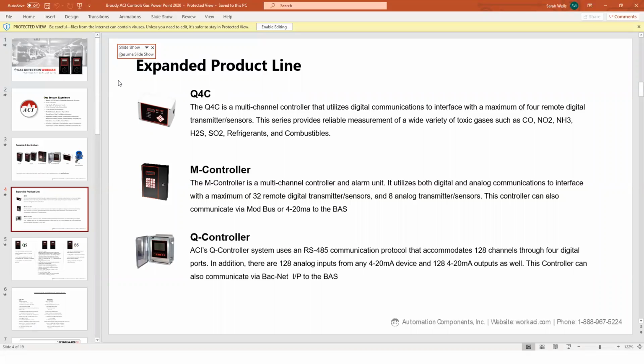The 3 different controllers, we just kind of covered those. Q4C, which is a 4-channel, multi-channel controller, digital communication, just for really, really small jobs. For the cost, I tend to stay away from it. I tend to try to push customers into the M controller. It's more flexible with the inputs, outputs, and the 32 remote digital covers a lot more projects. You can also have analog output cards, and why you would want that would be, let's say you've got a parking garage and you have VFDs on the fans and you need to control them through our controller and not the BAS. And this can be either Modbus or 4 to 20 back to the controller. The Q controller, same concept, handles up to 128 points digitally or analog inputs, and also can communicate BACnet IP, if that's what your customer is looking for.